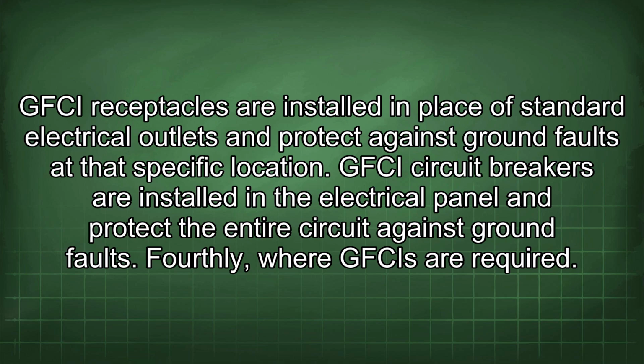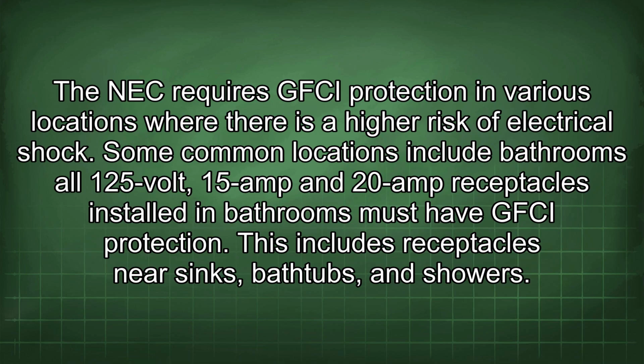Fourthly, where GFCIs are required. The NEC requires GFCI protection in various locations where there is a higher risk of electrical shock. Some common locations include bathrooms. All 125 volt, 15 amp and 20 amp receptacles installed in bathrooms must have GFCI protection. This includes receptacles near sinks, bathtubs, and showers.